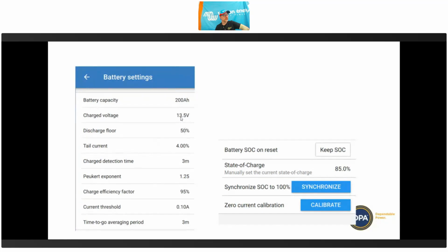The main one we're interested in is the charged voltage. And remember I said before that the battery monitor needs to recalibrate when a set of conditions are met for what it decides is fully charged. And remember, we're talking about renewable energy systems, so we're not talking about something which is mains connected most of the time and has a really reliable charge source. So it's easy to make a mistake when you're setting this up and put the absorption voltage, say 14.4 for a 12 volt battery. Actually, the default value, 13.5 for 12 volt, is about right, because this is the voltage that it's going to reset to 100% when it sees that voltage.